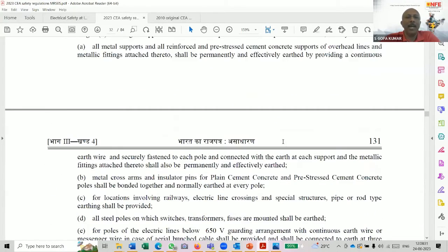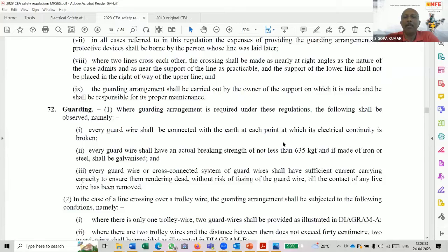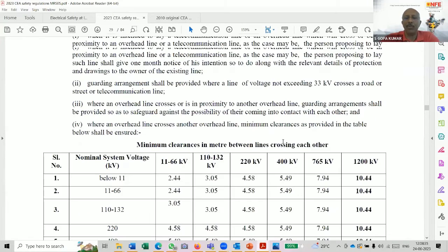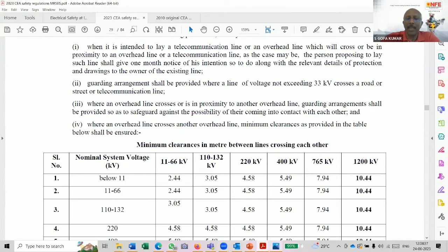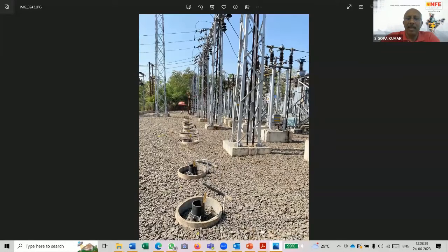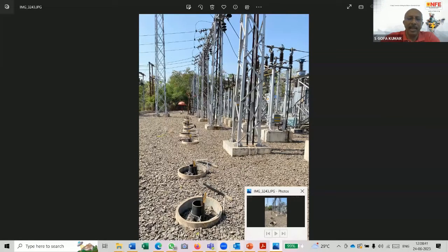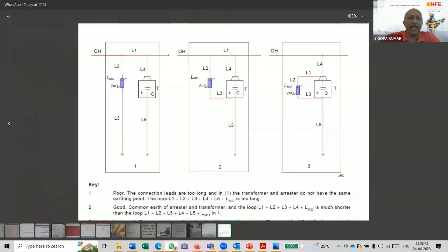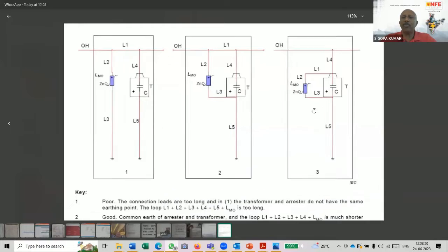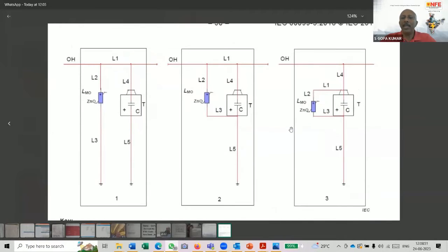For example, in Maharashtra, there are transformer terminal mounted surge arrestors as well. That means there are cases where this kind of connection is made. So connection number 3, in the 11 kV transformer, is also followed in Maharashtra, which is, I would say, very good.